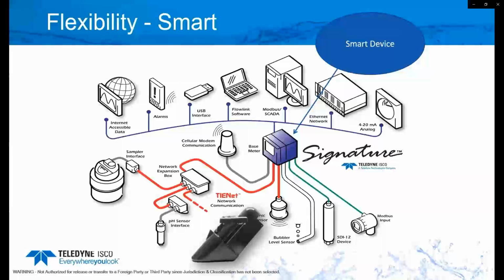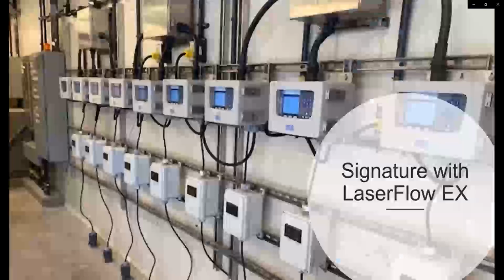A lot of capabilities here, so we can pick and choose other options we want. A lot of times people may even want to use this platform to move data, so they'd hook up, let's say, a magnetic flow meter that might have an analog output or a Modbus output, send it to the meter, it stores it, and can transmit it via the internet to the web-based stuff. It can also send an analog output to your SCADA system as well. So a lot of capabilities with this design.